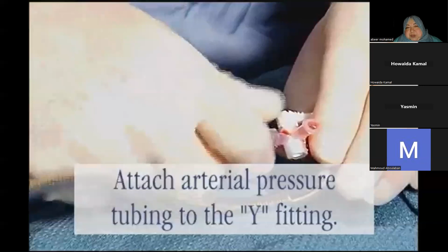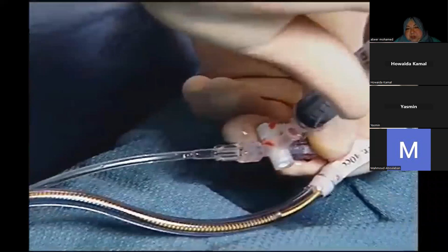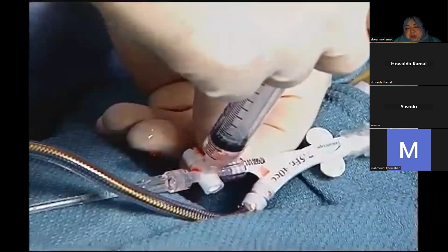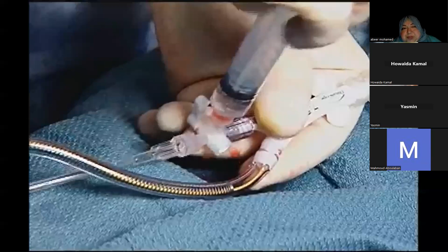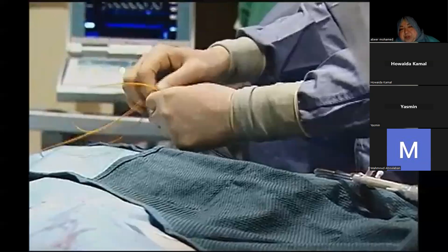Attach the arterial pressure tubing to the Y fitting. Release the vacuum from the balloon by removing the one-way valve and attached gas lumen insert. Connect the male luer fitting of the balloon to the catheter extender. Attach the male luer of the extender to the pump console and initiate pumping.